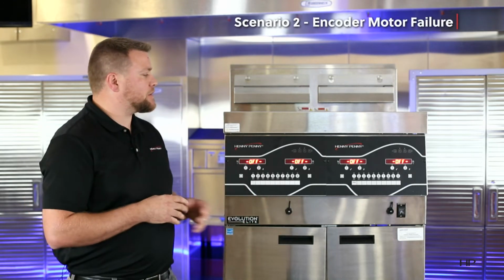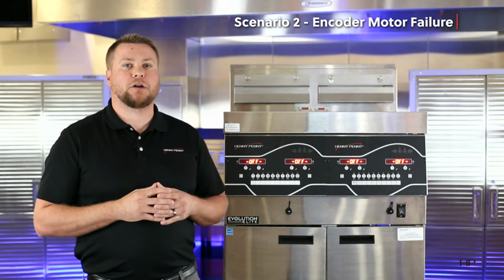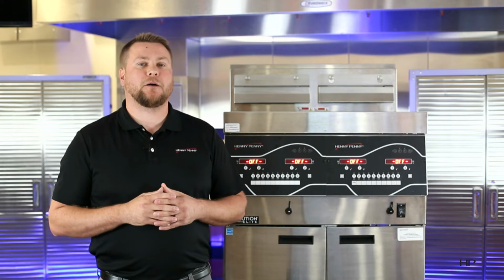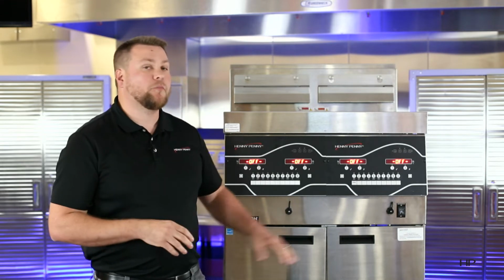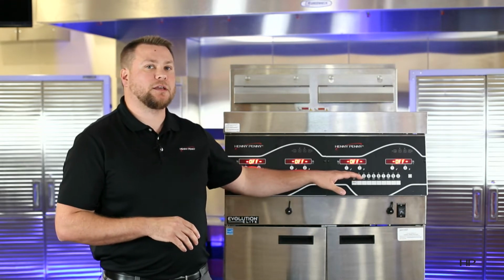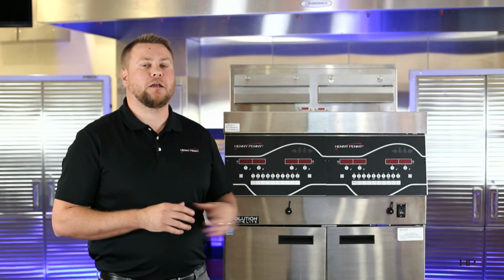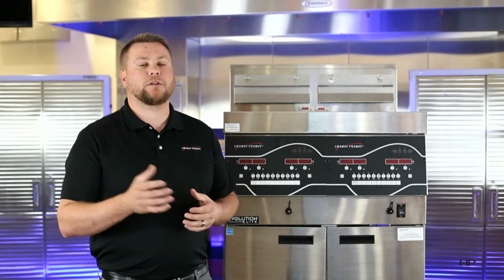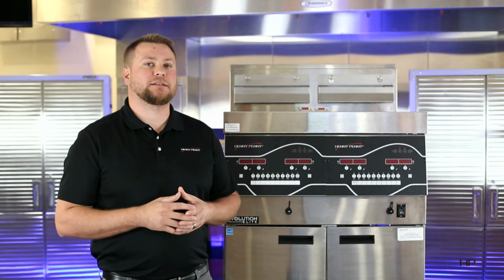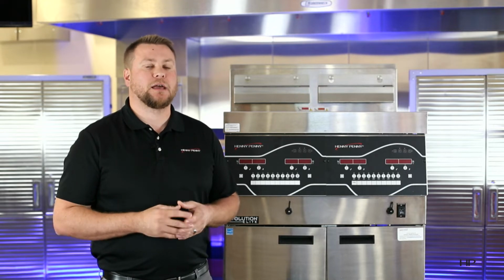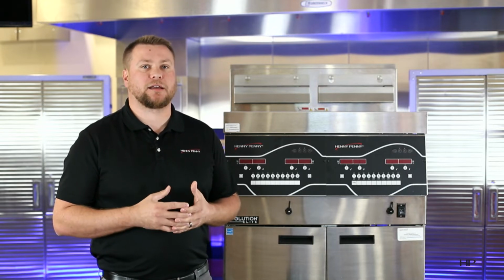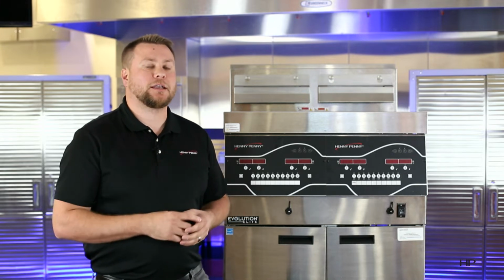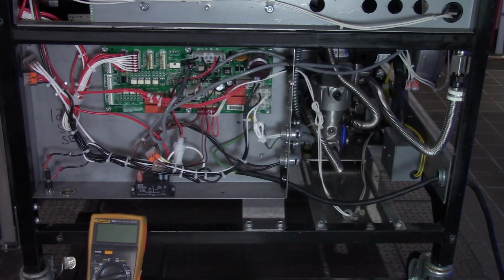So let's talk about the other situation. Let's say we come into the store, we turn our main power switch on, and we don't hear anything. Well, this is where we need to be ready to get our multimeter out and do some additional troubleshooting. But before we do, the most important thing is we want to make sure that we power this main power switch down before we start unplugging or plugging anything in related to the control board or the AIF board, as this can easily damage components on any one of those boards, as the electronics can be sensitive to that kind of activity. So let's go ahead and go over here to our next stage and we'll do some troubleshooting.